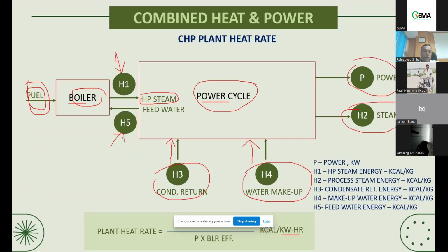So if you see that boiler inlet, if you see this energy, when I'm giving it at say 120 degree centigrade, I am giving a lesser energy to the boiler, and when I'm giving 200 degree centigrade or maybe 190 degree centigrade, then I am giving a higher energy back to the boiler, and obviously for that there is some power loss. So if you do the math, you will find my overall fuel consumption is going to reduce.